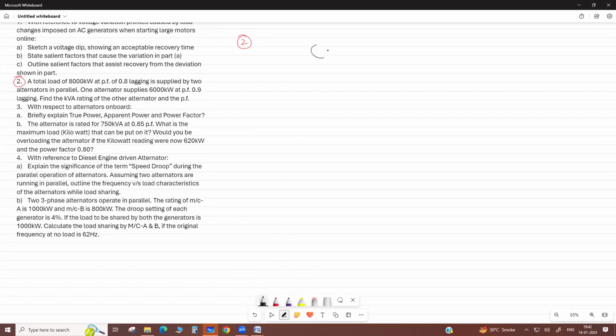He said there are two alternators or machines, machine 1 and machine 2, or you can say A and B. Machine A and B are operating in parallel and sharing a total load. Here the total load is 8,000 kilowatt at a power factor of 0.8 lagging.